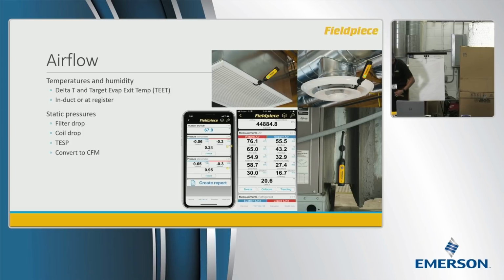So you can hook it up somewhere with a strong magnet there into the return airflow, and then out the supply with the magnet there. And with two of those, you are getting your dry bulb, your wet bulb, your humidities, your dew point, your enthalpy, and your delta T all in the palm of your hand, and it didn't take more than a couple seconds. Also, the app performs a target evaporator exit temperature test, which means it looks at the humidity and the temperature on the return side, and it calculates what the supply air is supposed to be on the outside.